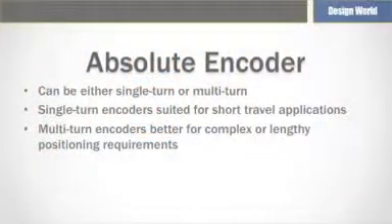Another feature is that absolute encoders do not lose position whenever power is switched off. Since each position is distinctive, the verification of true position is available as soon as power is switched on. So it's not necessary to initialize the system by going back to a home base for a reference.